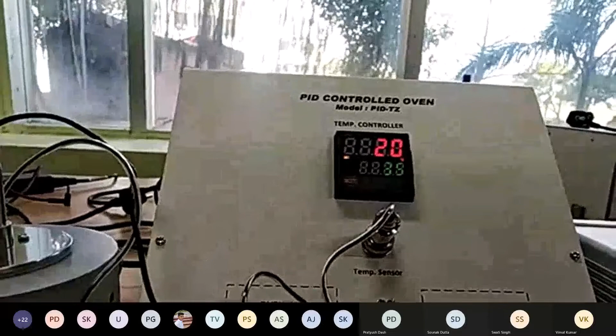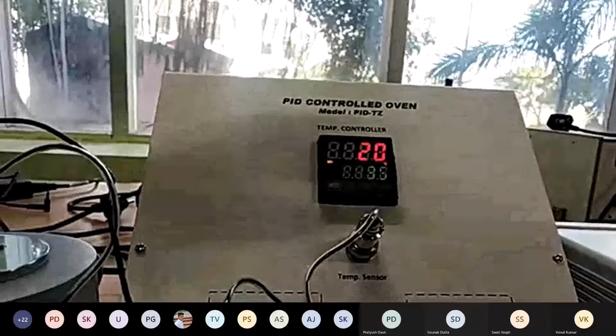The temperature is 20 degrees centigrade, and below this is SV, the set value. We set a particular value, and the controller calculates the temperature difference. That difference is executed through PID, meaning proportional, integral, and differential control, which then increases the temperature at a particular rate. The temperature difference is continuously calculated in a loop, and the temperature is increased accordingly at that rate.